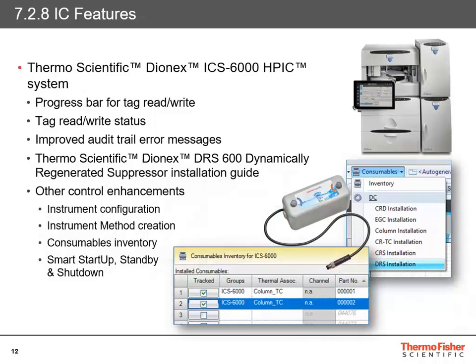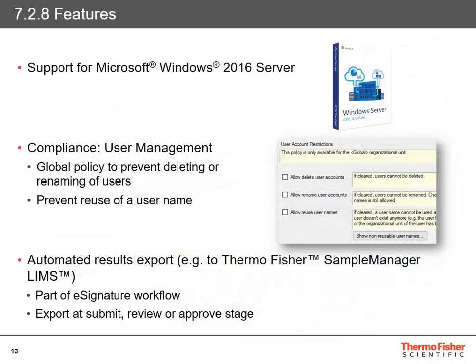Other enhancements for control of the ICS-6000 have been made in instrument configuration, creation of the instrument method, handling of the consumables inventory, and Smart Startup, Smart Standby, and Smart Shutdown are now supported. Chromeleon 7.2.8 has been tested and validated on the Windows Server 2016 operating system. It also introduces new compliance policies: a global policy to prevent unit administrators from deleting or renaming users has been added, and a new policy preventing the reuse of a username is now available. This ensures usernames cannot be reused even if previously assigned, renamed, and deleted — guaranteeing all usernames will be unique for the entire lifetime of the software. Version 7.2.8 also introduces the ability to clone access groups and roles, making it easier to create a new role or access group that only differs in a few options from an existing one.